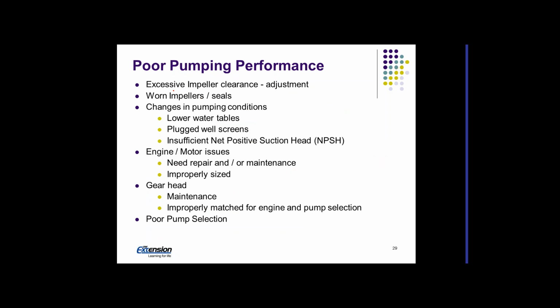Poor pumping performance can be a factor of wear on the impeller or seals, and we're going to talk a little bit about how they can adjust those, because that can be adjusted. We're basically going to look at pumping conditions like water levels and plug screens and stuff. So if the well's not supplying enough water, it could be a plug screen. If we looked at the drawdown between when the pump was put in and how we're using it now, you may find that the water's not coming in as fast. So that could be a problem with plug screens. And that's an issue with having that insufficient net positive suction head requirement.